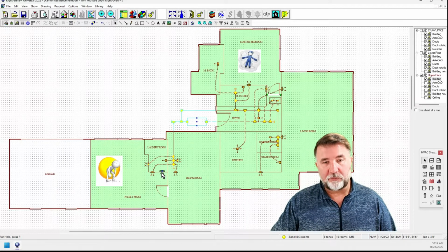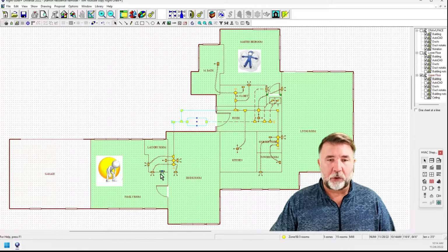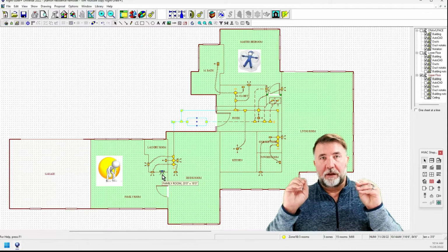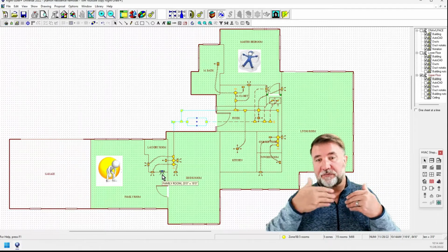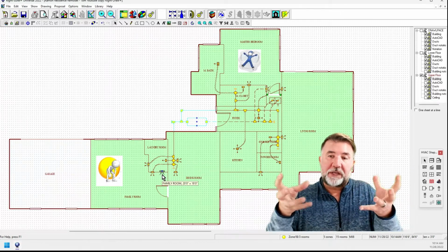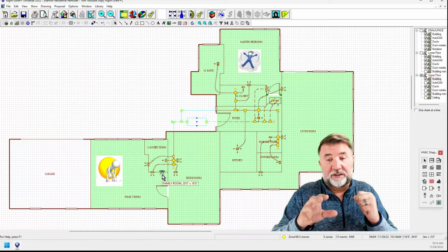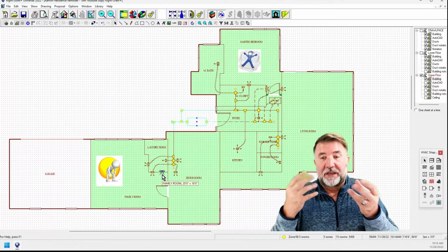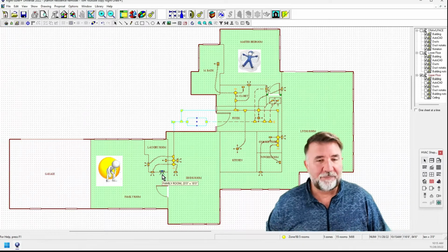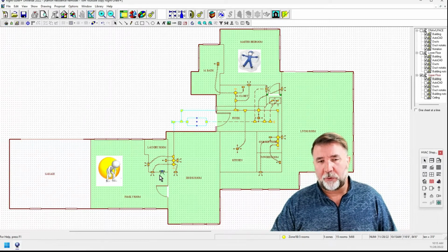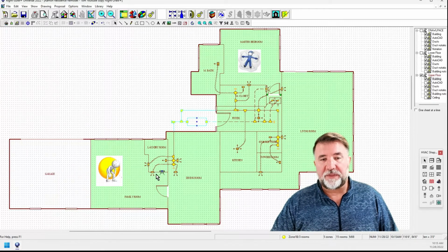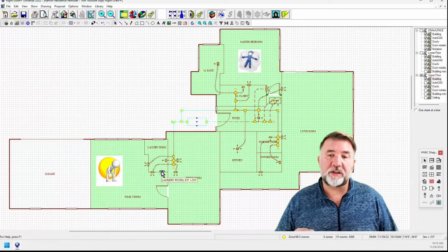So right here, you see a return. Now this is set up in the laundry room because there are codes that require that in laundry rooms you have additional air to pass through if the doors are closed, so that you have that air exchange. Because when the dryer comes on, the dryer is actually pulling air out of the house and pushing it outside. It doesn't just miraculously make its own exhaust, because obviously we have the exhaust that goes out. Everybody's had that issue where it gets blocked up and they have to clean it out. So this is just a little transfer vent to help allow air to go through if this laundry room door was closed. But this right here is called a transfer grill.